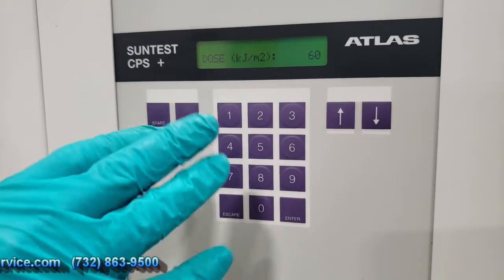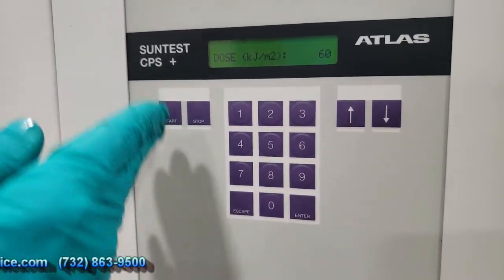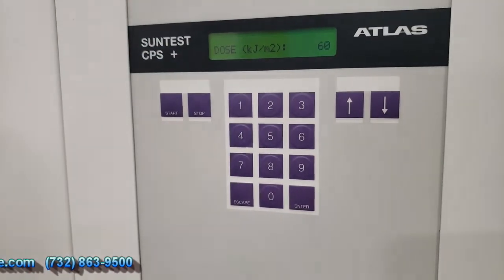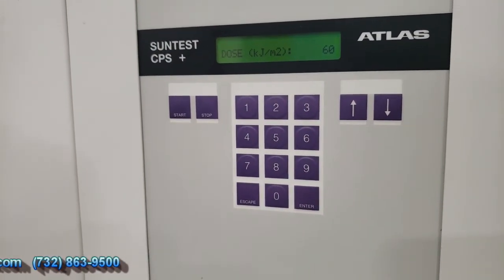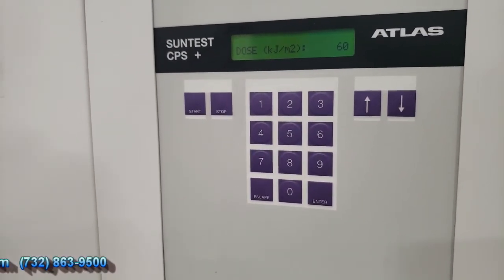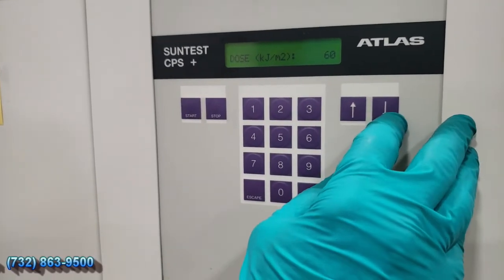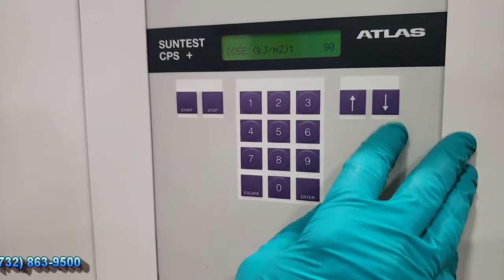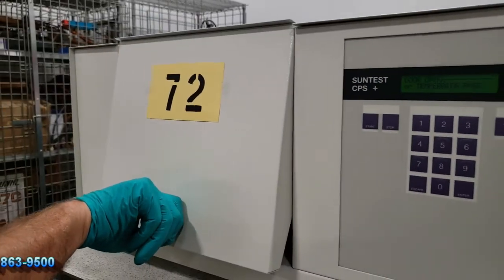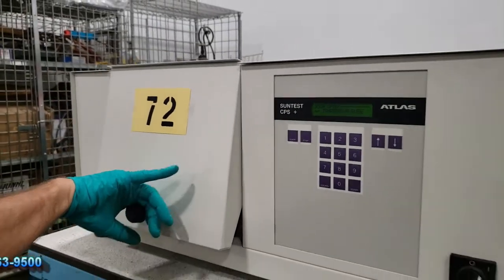So there's two ways of stopping the program. One is through time, the other is through a dose. So in a program, you can set it to a dose setting. Say you want 500, it'll run up to 500 and then shut off. And the other thing, just to show you, if you ever try to open a door, it'll automatically shut the lamp off for you.